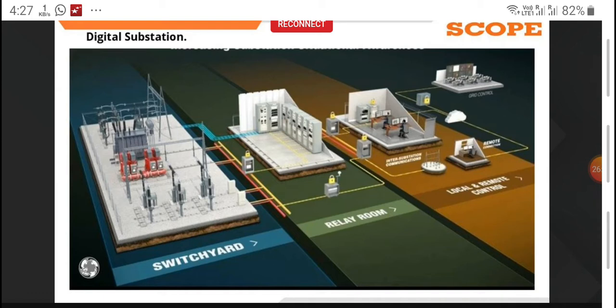If you see the switch yard, all your CT, PT, lightning arresters, transformers and breakers, these signals are carried through optical fiber to the relays, and the relay has a special module which accepts the digital signals from the CT. Today's conventional CT gives a 1 ampere secondary current, but when it comes to the digital CT or electronic CT or optical CT, or optical PT, what happens?